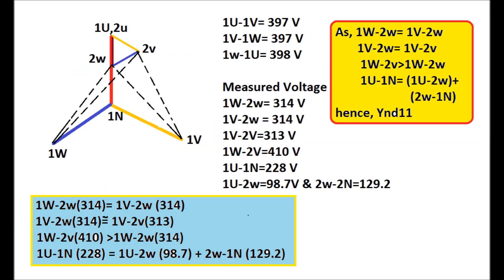The criteria for YND11 differ slightly from YND1. Number 1 — voltage between 1W and 2W must equal voltage between 1V and 2W. Number 2 — voltage between 1V and 2W must equal voltage between 1V and 2V. Number 3 — voltage between 1W and 2V must be greater than voltage between 1W and 2W. Number 4 — voltage between 1U and 1N must equal the sum of voltage between 1U and 2W plus voltage between 2W and 1N.